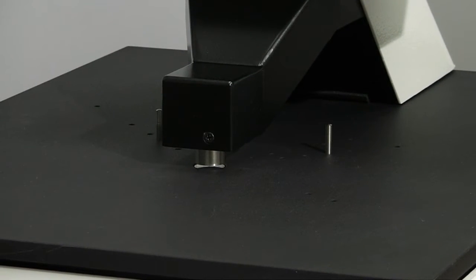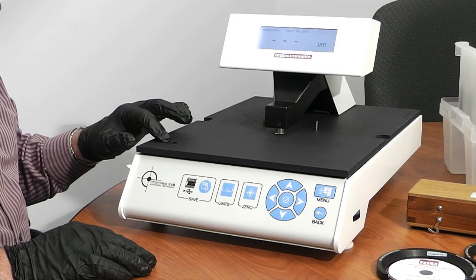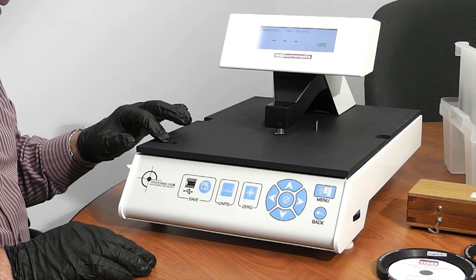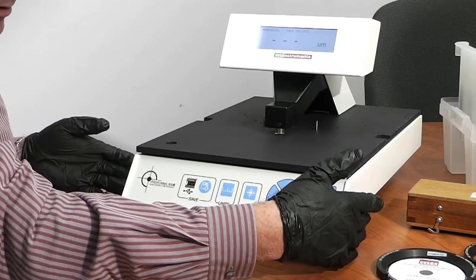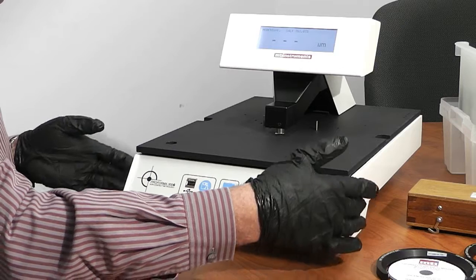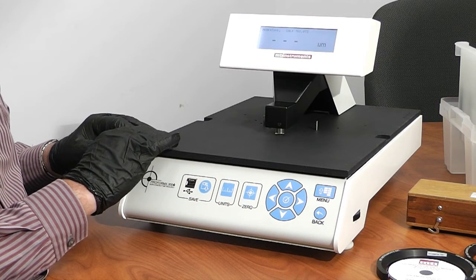We also have pins on here, and the pins allow us to set a fixed distance, so that when we measure the wafer, we always measure the ring to the same. We also have a bubble level that's built into the top deck, and what we can do is level up the deck by adjusting these two adjustments here. There's two feet that are on the bottom, and by raising and lowering these, we can get all the tilt out and get the top deck centered.